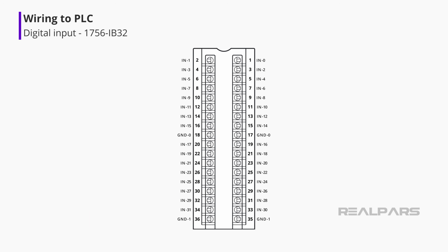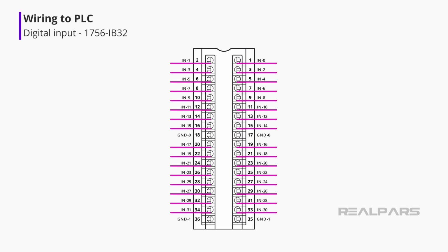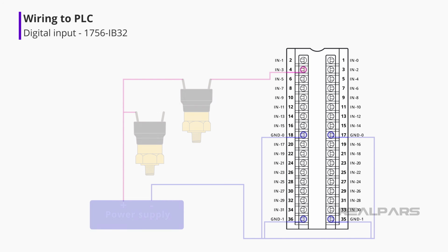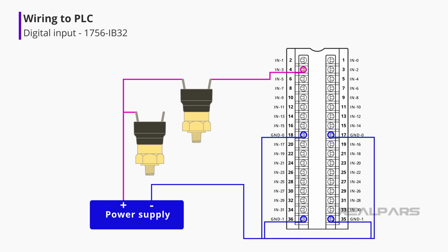The 1756-IB32 module is capable of supporting up to 32 digital input devices. Each additional device would be wired the same as the GEMS pressure switch. One terminal of the new device would connect to the positive DC terminal of the power supply, and the other device terminal would connect to any of the remaining open inputs on the digital input module.